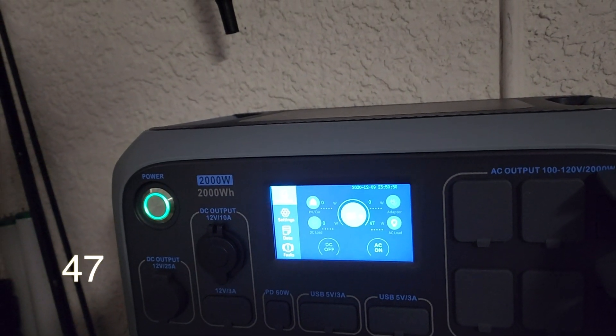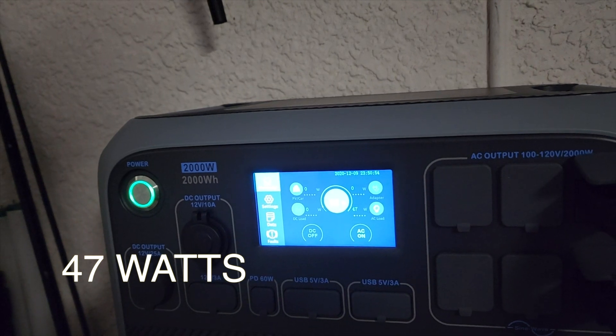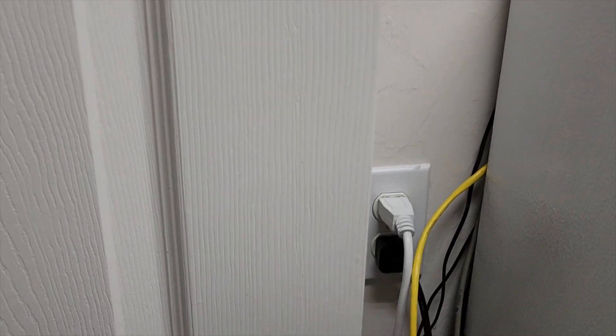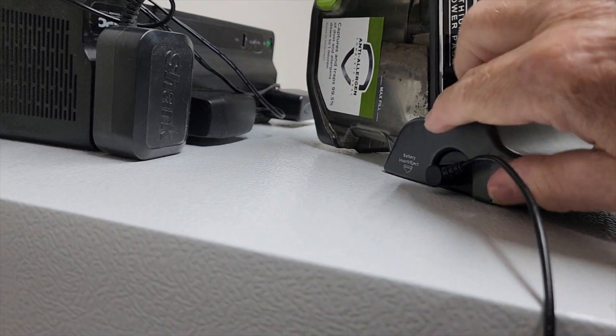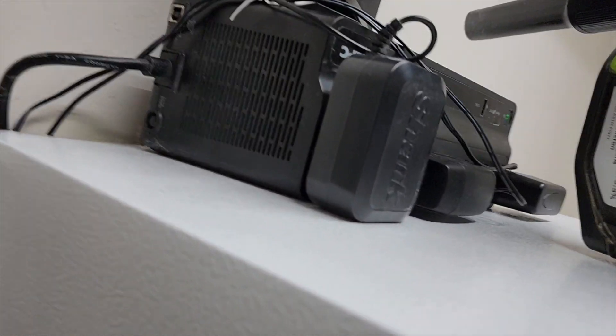I just switched the transfer switch over and we're pulling 47 watts, which is just the basics for that room. Let's go in that room now and check it out. I'll be disconnecting this stand-up freezer for this test — I don't want any extra amperage — and I'm also going to be disconnecting this unit from charging.